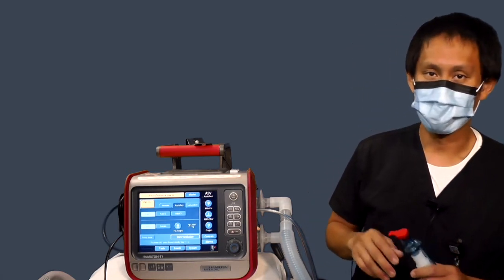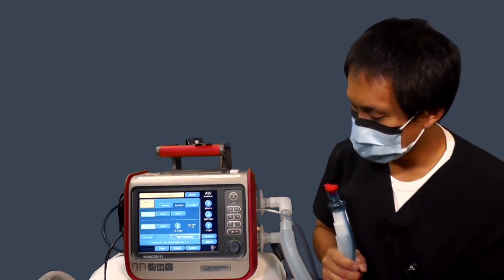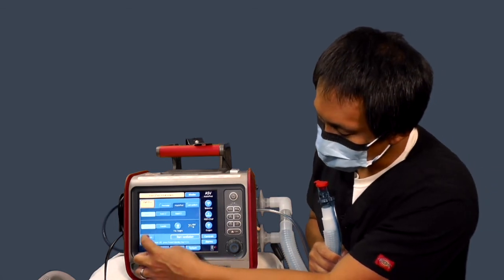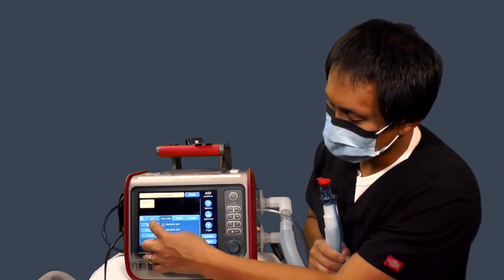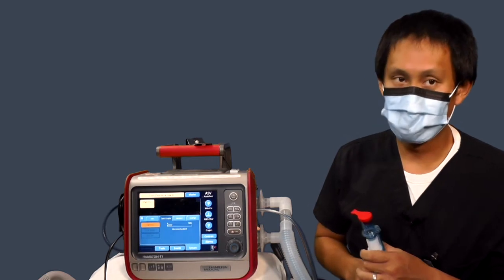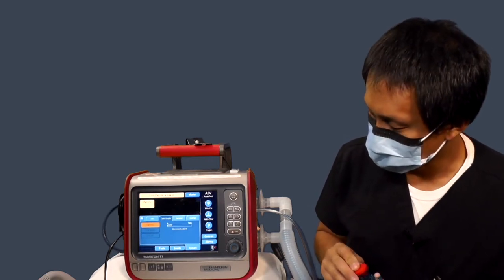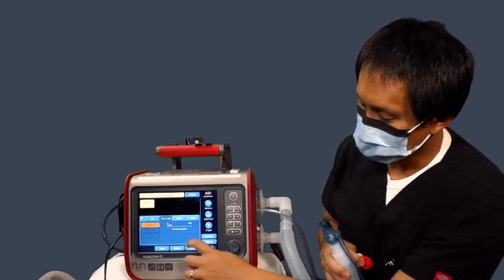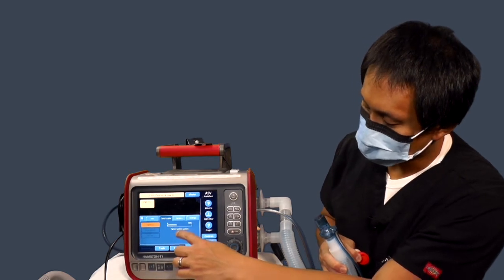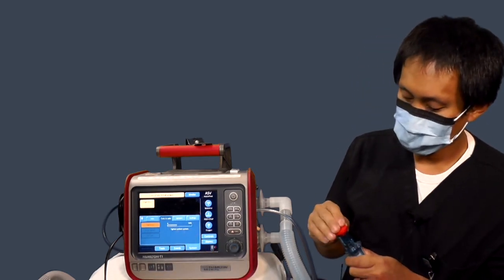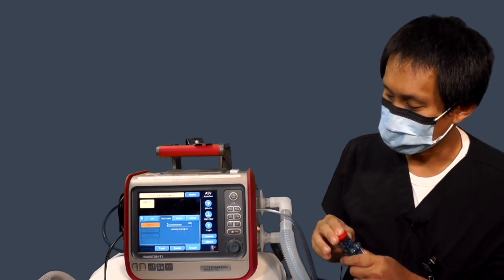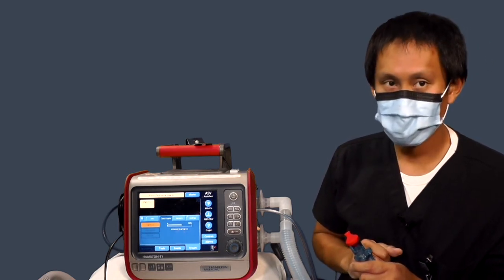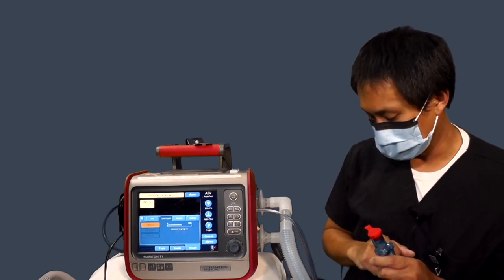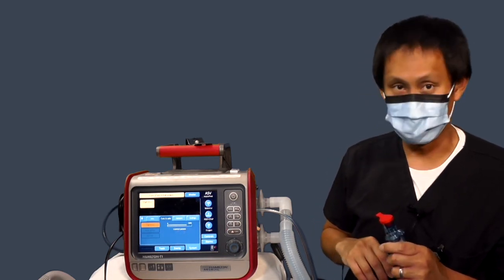All right, so we're going to start with the pre-use check. We're going to start with the tightness test. So make sure you're following the prompts on the screen. The prompts are located down below the bar right here. So now I'm going to tighten the circuit, and what it's doing is checking for compressible volume in this circuit.